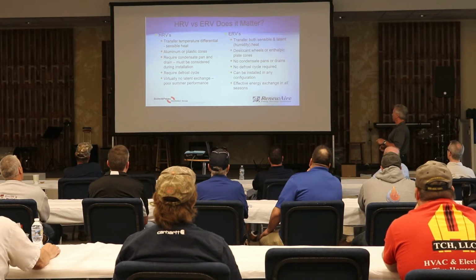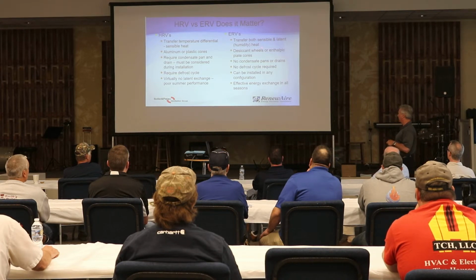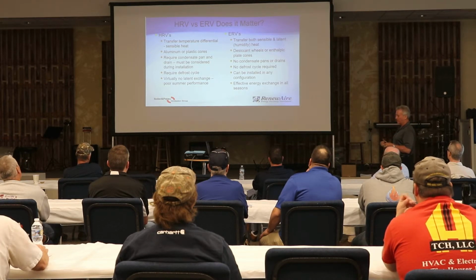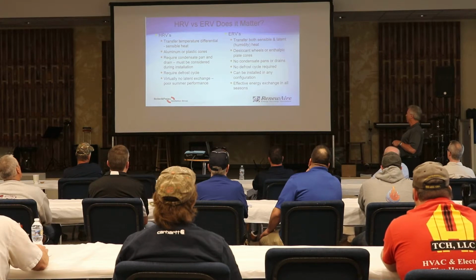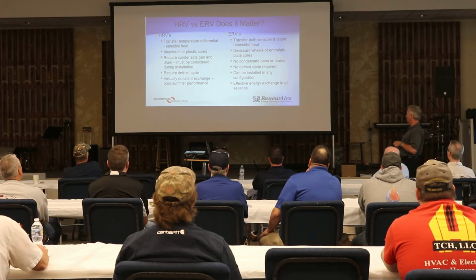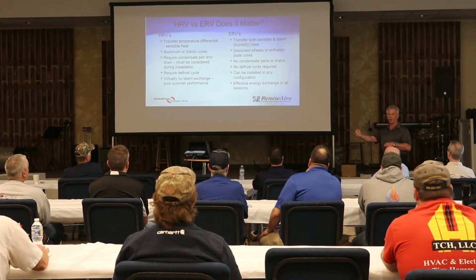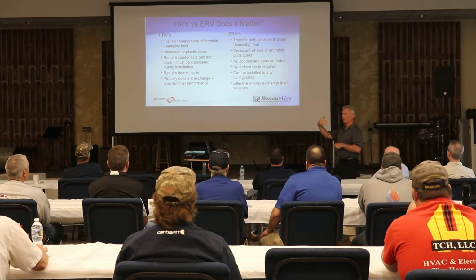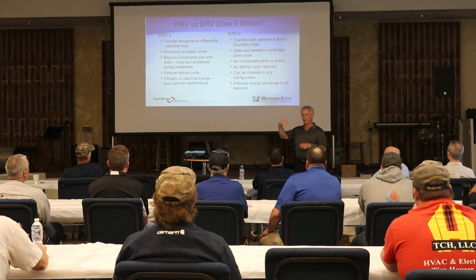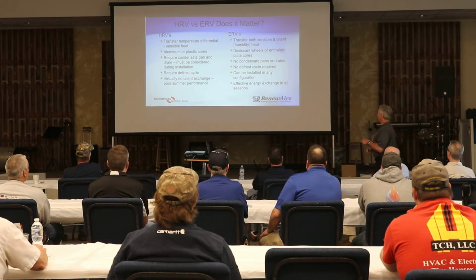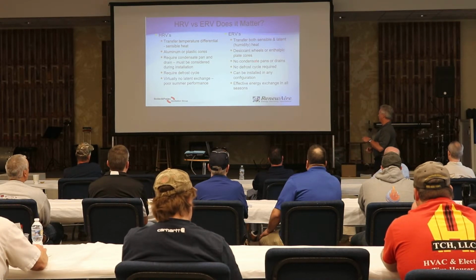We'll contrast that with energy recovery ventilators now. First of all, the most important thing is they transfer both sensible and latent heat or humidity. The two methods, as I touched on, are desiccant heat wheels or enthalpic plate cores. What we'll talk about today are enthalpic plate cores. There are no condensate pans or drains required. There is no defrost cycle. There is no frosting in the core. Entrained water vapor will transfer through the plate from one airstream to the other. We'll show you how that happens. But because of that, these two things are not required.